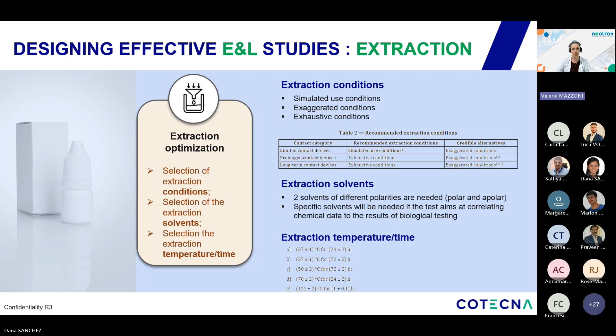And by balancing these factors, conditions, solvent strength, temperature, and exposure duration, we ensure that our extraction studies reveal the true chemical risk while staying scientifically justified and relevant to clinical use. So moving to the second point, so to the detection. Effective detection relies on combining screening and targeted analytical approaches to build a complete and reliable chemical profile. So screening is our broad exploratory step using high-resolution full scan technique to capture as many chemical signals as possible, including both unexpected or unknown compounds. And it allows us to see the full landscape of what might be present without assumption or predefined targets.